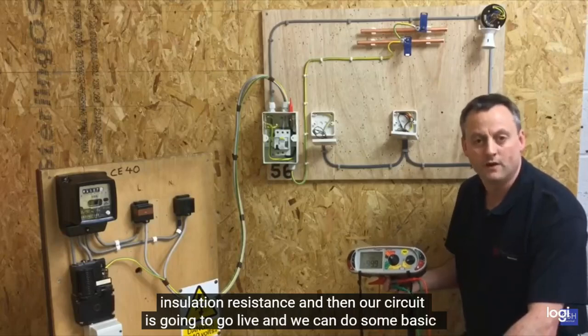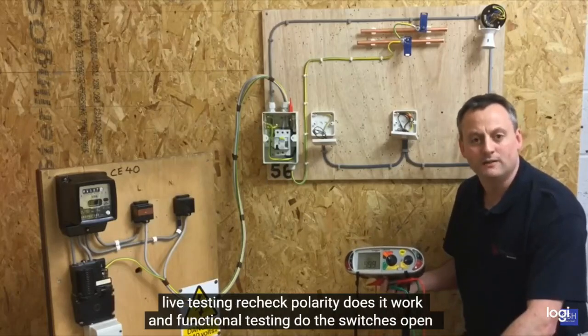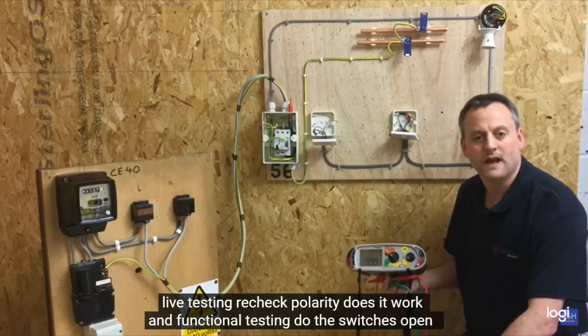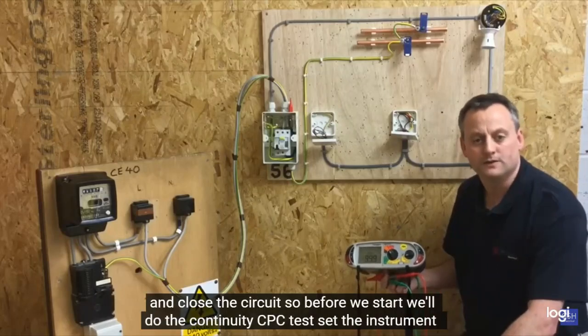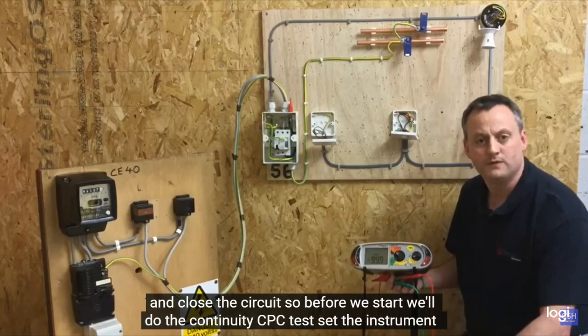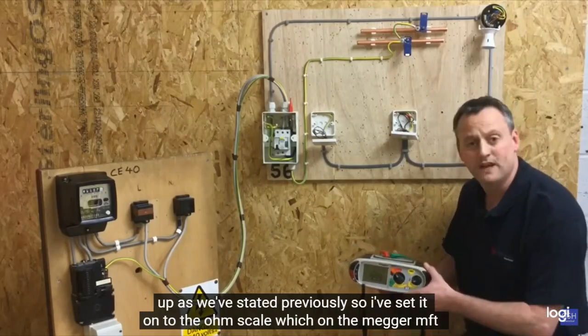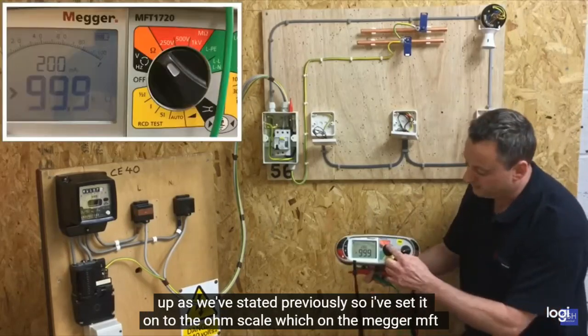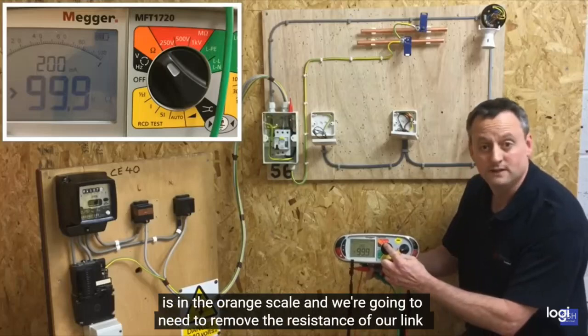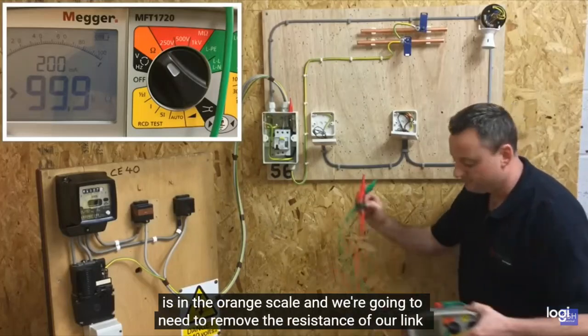Before we start, we're going to do the continuity of CPC tests, using an instrument that we've stated previously. I've set it onto the ohm scale, which on the Megger MFT is the orange scale, and we're going to need to remove the resistance of our leads. We've stated this in previous video presentations. I'm going to link together the crocodile clips, which are in the red and green sections at the top of the instrument we've talked about before.